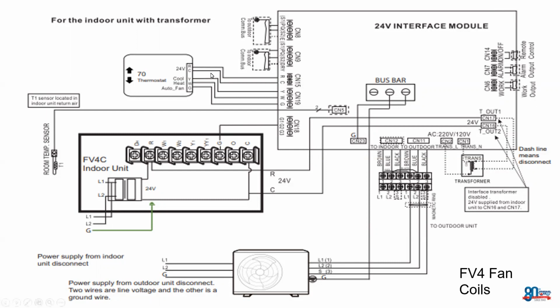Okay. Now that signal is sent via the third-party thermostat into the interface, which then interprets that Y call or that W call, and then communicates that via the signal line to our outdoor unit to let it know that it has an active call for cooling and an active call for heating.